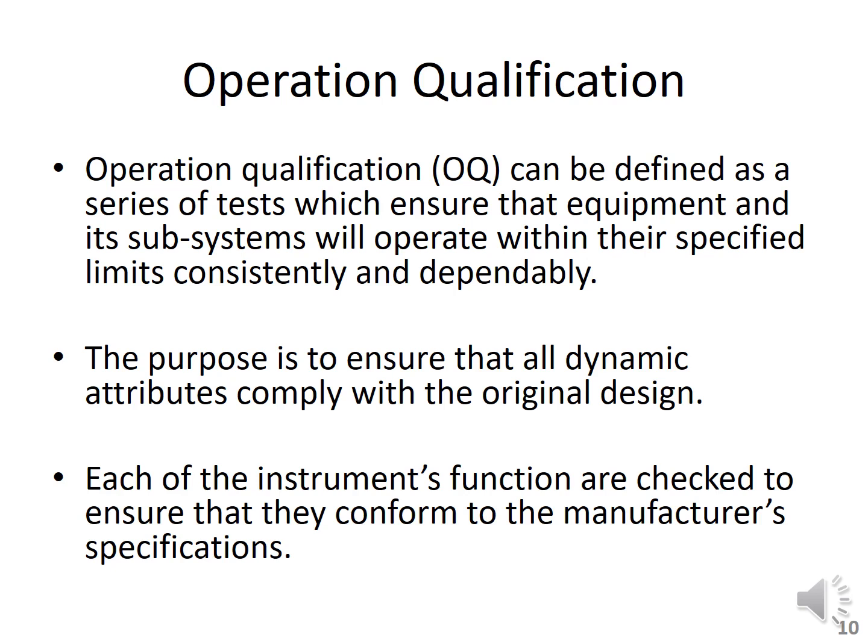Operational qualification is usually performed before the system is released for use, right? This is very important. This is usually performed before the system is released for use by the customers, by the consumers. Or in other words, if you are talking about an instrument, we would say that operational qualification is usually performed before the instrument is handed over for use, right?